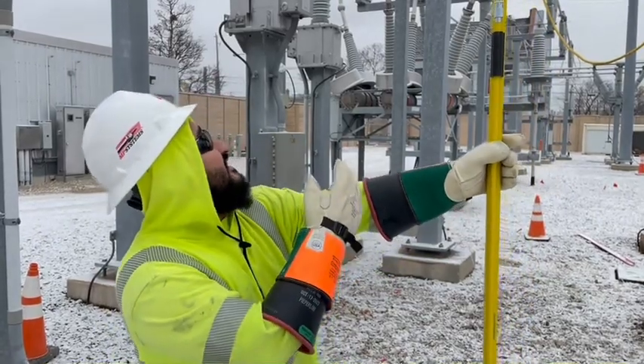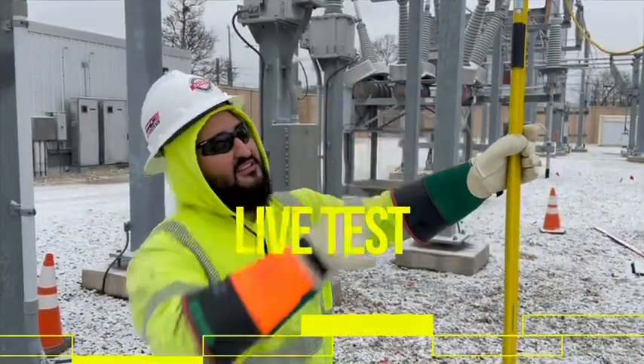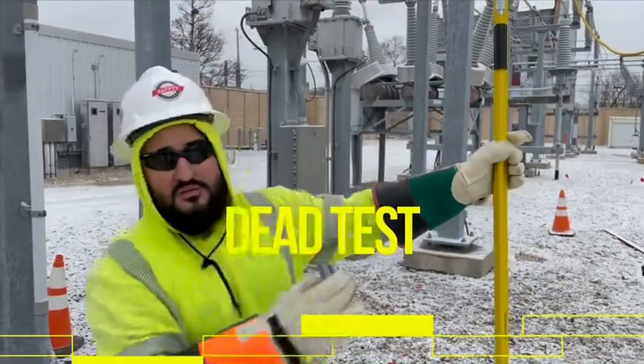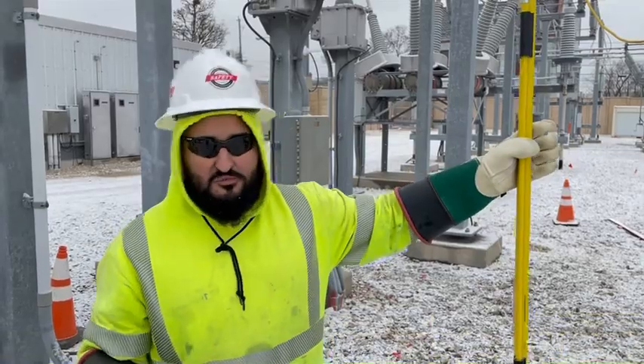I just finished up grounding our dead line. What I did first is I tested live — that side of the bus is live. Came back, tested dead, to make sure that our line where we're going to be doing work is dead. Then went back, tested live again, to make sure that nothing happened to the tester in between those points.